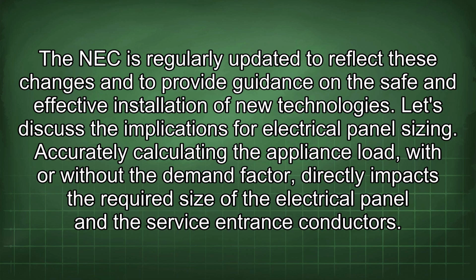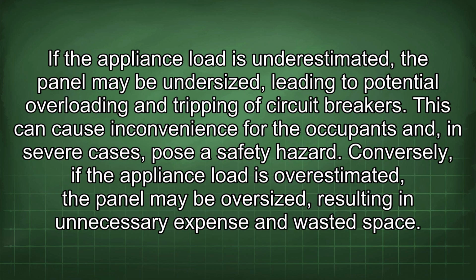installation of new technologies. Let's discuss the implications for electrical panel sizing. Accurately calculating the appliance load, with or without the demand factor, directly impacts the required size of the electrical panel and the service entrance conductors. If the appliance load is underestimated, the panel may be undersized, leading to potential overloading and tripping of circuit breakers. This can cause inconvenience for the occupants and, in severe cases, pose a safety hazard.